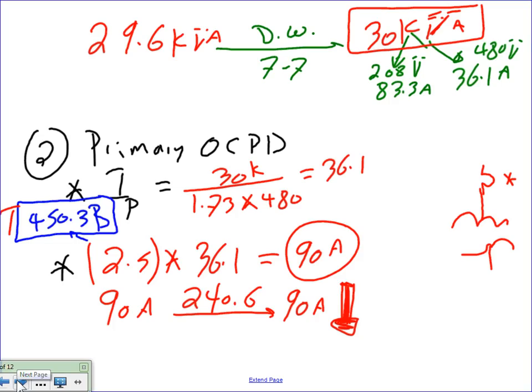I went down because if you go to 450.3(B), it doesn't have note number 1. Remember, guys, note number 1? And note number 1 tells you if it's not a standard, go up. So if it doesn't tell you to go up, let's go back to the 3 options. Anybody remember the 3 options? If you can't go up, custom design yourself. In this case, it's 90, so you really hit the jackpot. But say if it was 89. No, it was 91. Say it was 91.